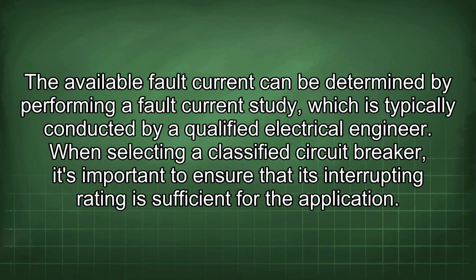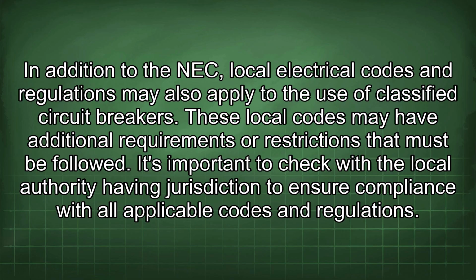When selecting a classified circuit breaker, it's important to ensure that its interrupting rating is sufficient for the application. In addition to the NEC, local electrical codes and regulations may also apply to the use of classified circuit breakers. These local codes may have additional requirements or restrictions that must be followed. It's important to check with the local authority having jurisdiction to ensure compliance with all applicable codes and regulations.